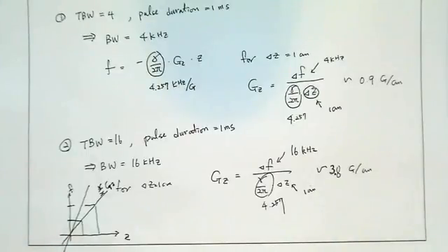So depending on the gradient amplitude and bandwidth, that's going to determine your slice thickness. In other words, for a given slice thickness, you have to change either gradient amplitude or the RF bandwidth.